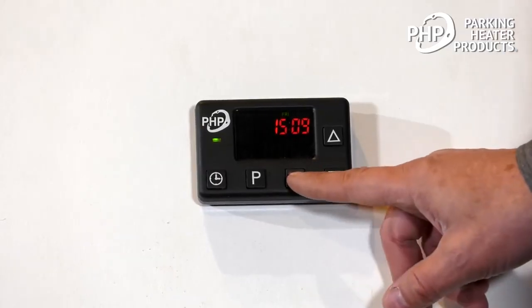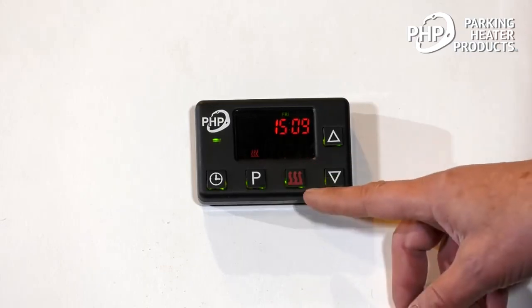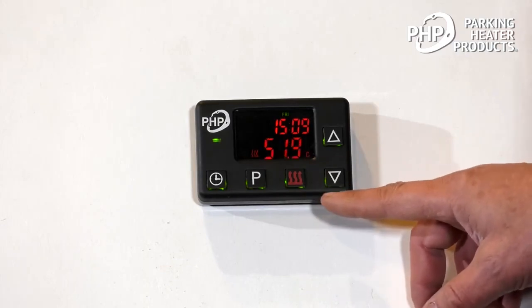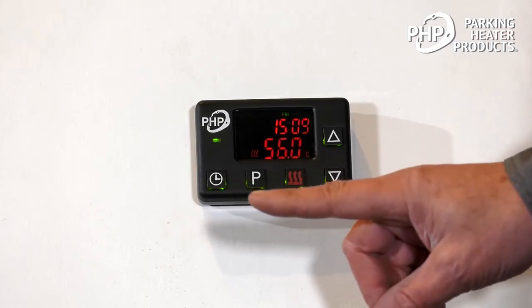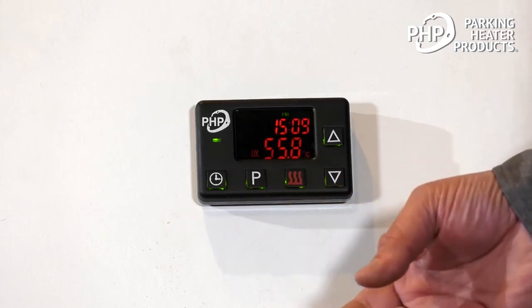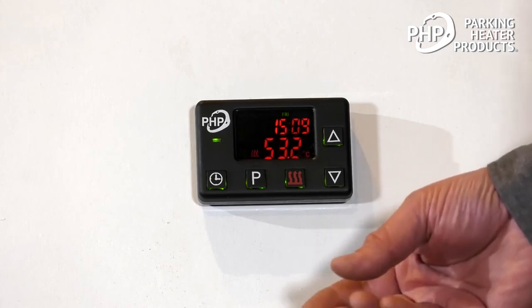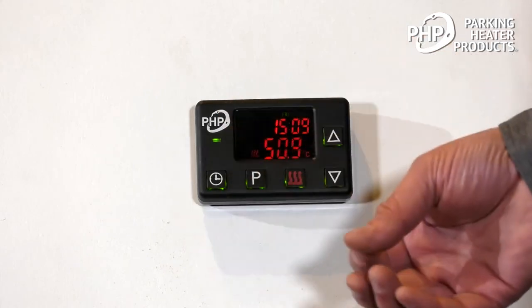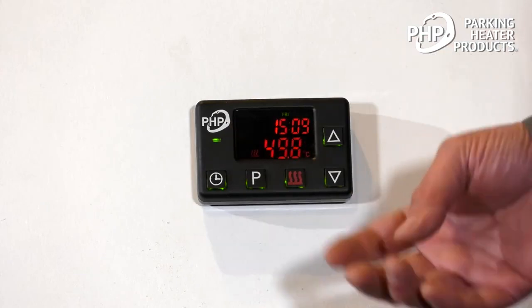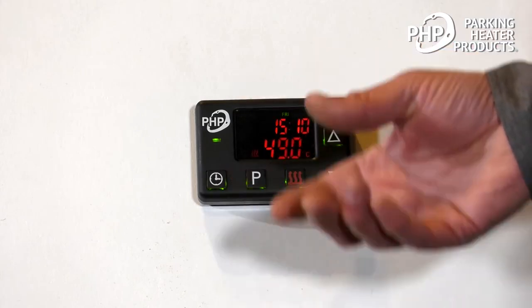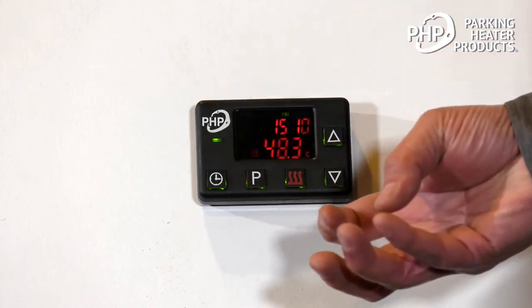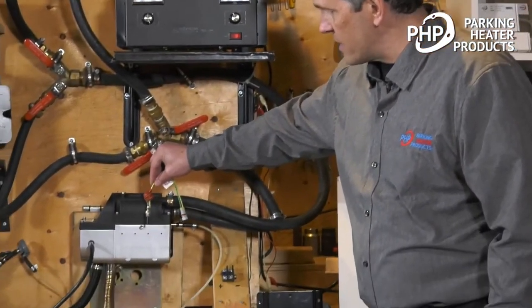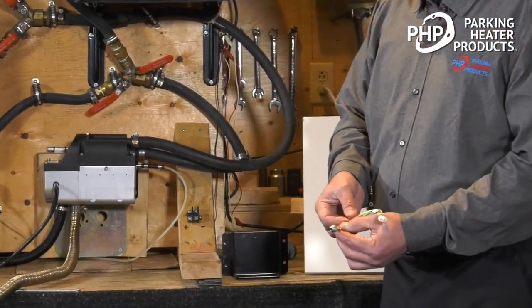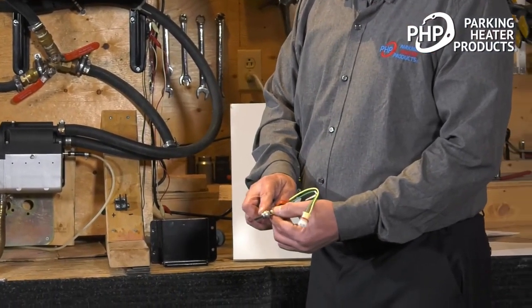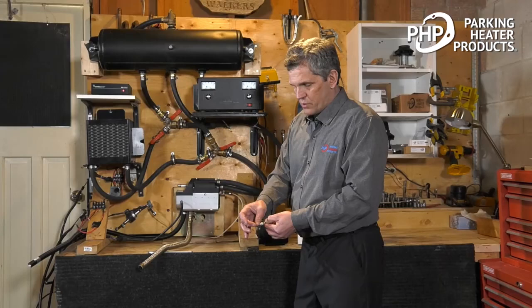To turn the heater on, we simply press the heat button momentarily. The first thing that happens is the heater does a systems check. It checks the voltage to make sure that the voltage is between 11 and 15 volts. It makes sure that the heater does require heat. It checks all of the components, the glow pin, the sensors, to make sure that everything is intact. The next thing that happens is the glow pin, which is located inside the heater, starts to get preheated. This is just an electrical element. When we put 12 volts to it, this area gets red hot.